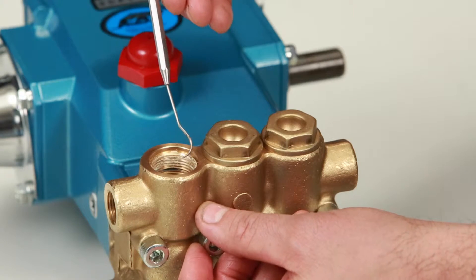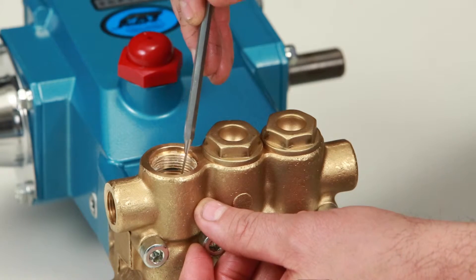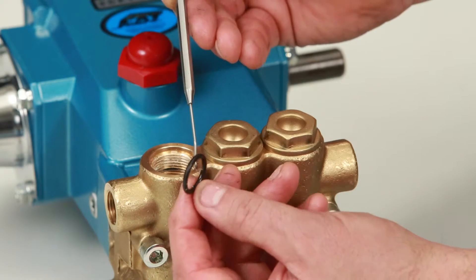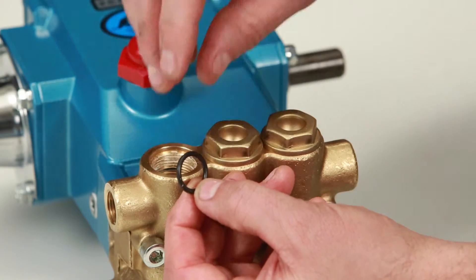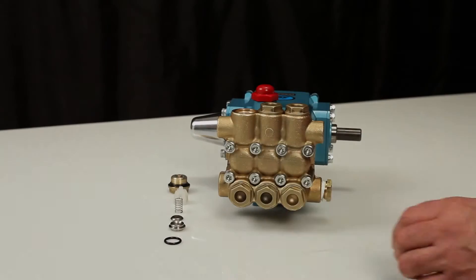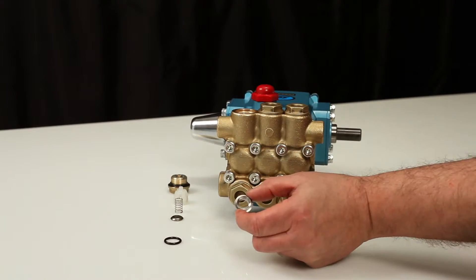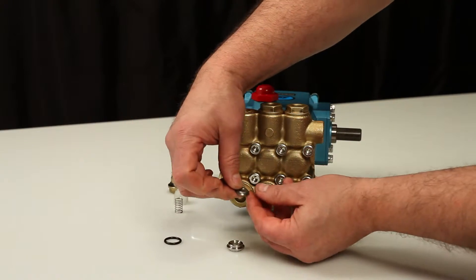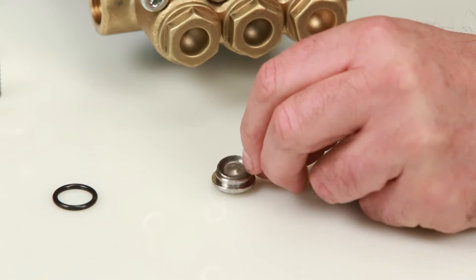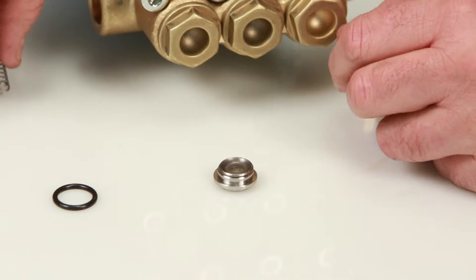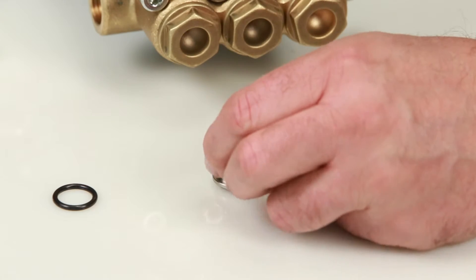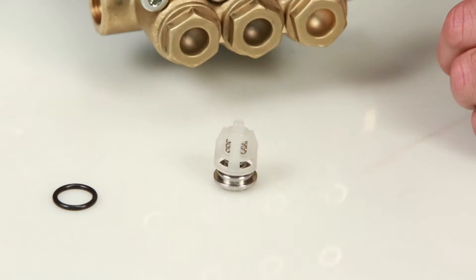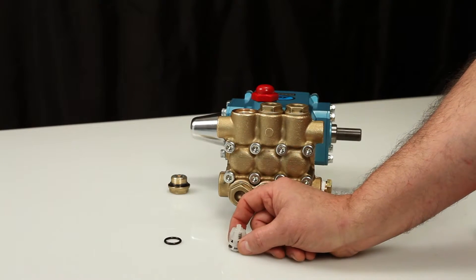Remove the O-ring from the manifold using a small screwdriver or pick. Inspect for cuts or nicks. To reassemble the valve assembly, place the valve seat on a flat surface with the tapered surface facing up. Place the valve onto the valve seat with the tapered surface facing down. Place the spring on the valve, followed by the spring retainer. Using a rubber hammer, lightly tap into place.